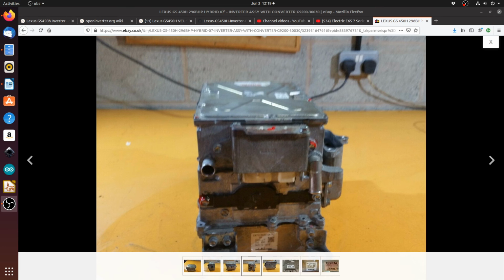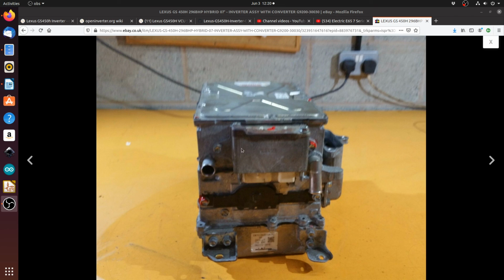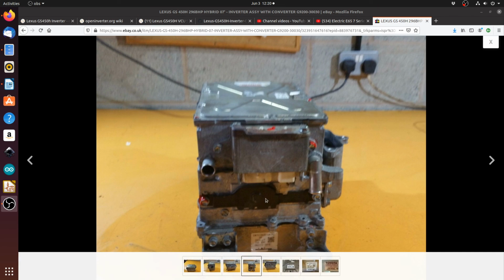Down here you'll see this black area, with a bolt here and a bolt here. If we remove those two bolts and take the metal panel off, there's a little plastic cover that sits here. If we pop the cover out, we get two M6 bolt terminals that are recessed in the inverter. Those terminals give us direct access to the main inverter DC bus in here, so we bypass the converter stage and go directly into the inverter.